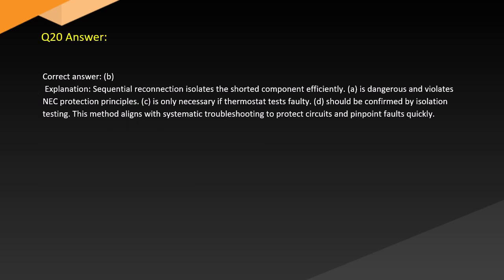Answer. Correct answer: B. Explanation: Sequential reconnection isolates the shorted component efficiently. A. Is dangerous and violates circuit protection principles. C. Is only necessary if the thermostat tests faulty. D. Should be confirmed by isolation testing. This method aligns with systematic troubleshooting to protect circuits and pinpoint faults quickly.